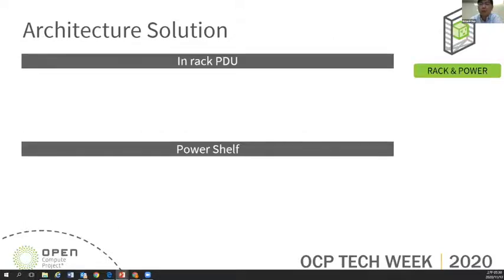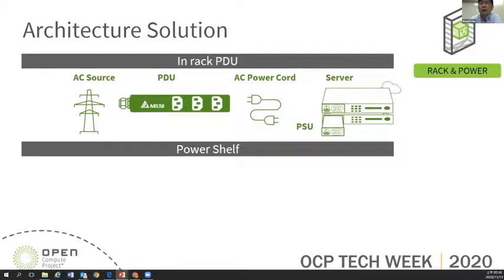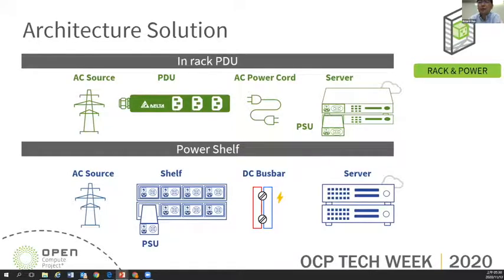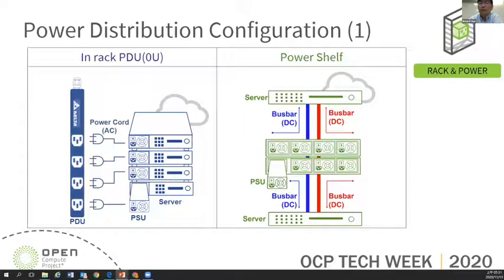When we talk about architecture, there are two kinds of power architecture solutions in the IT rack. The first one is we take the PDU, connect it with the data center AC power source, and use AC power cords to distribute the power to each server. The other one is similar to OCP, where we use the power shelf. The power shelf connects with the AC power and with the bus bar, and the bus bar provides a 12 volt or 48 volt bus, and servers can use a clip to connect to it. So for the rack type PDU solution, we put the PDU and use AC power cords to distribute power to each server, but for the power shelf solution, the bus bar, whether 48 volt or 12 volt, is what we use to distribute power to each server.